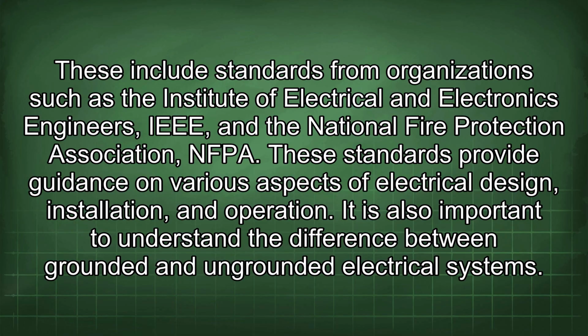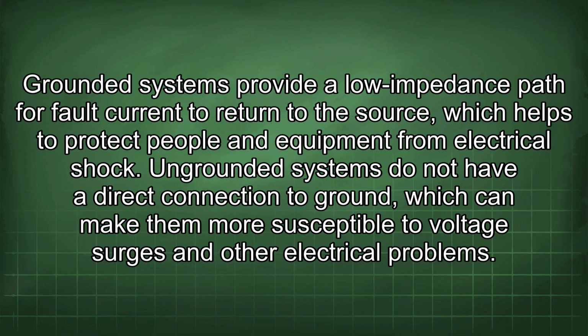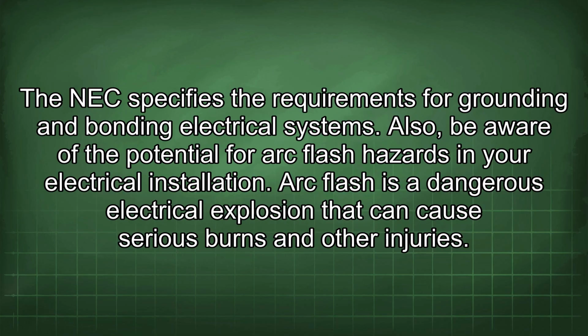It is also important to understand the difference between grounded and ungrounded electrical systems. Grounded systems provide a low impedance path for fault current to return to the source, which helps to protect people and equipment from electrical shock. Ungrounded systems do not have a direct connection to ground, which can make them more susceptible to voltage surges and other electrical problems. The NEC specifies the requirements for grounding and bonding electrical systems.